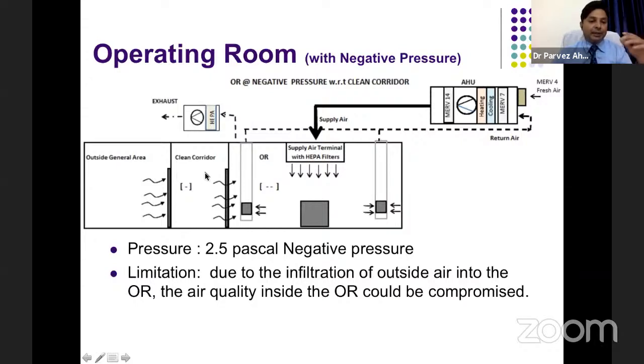Outside of the operation theater, there is a clean corridor. It also has more pressure than the operation theater, so that pressure comes inside and goes out through the HEPA filter exhaust system. We have to maintain 2.5 Pascal negative pressure inside the negative pressure operating room.